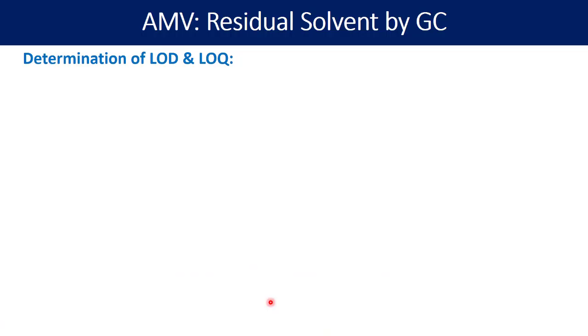The third parameter is the determination of limit of detection (LOD) and limit of quantitation (LOQ). There are three different ways to determine these: first by visual inspection, second by the slope method, and third by signal-to-noise ratio. Visual inspection is a traditional approach and not commonly followed today, so I recommend the other two approaches.